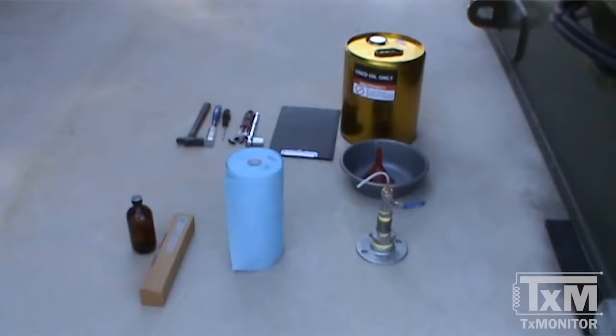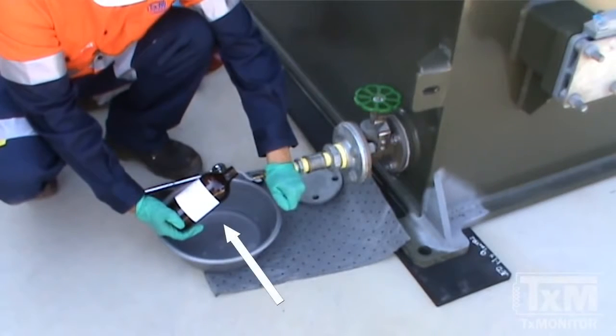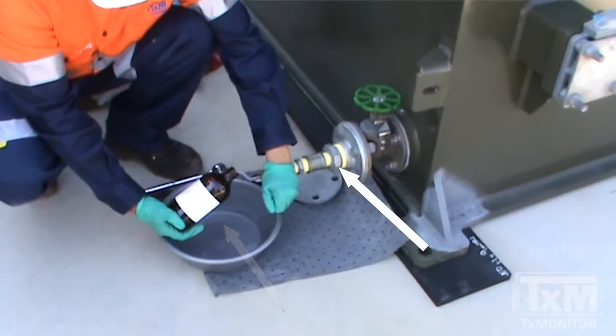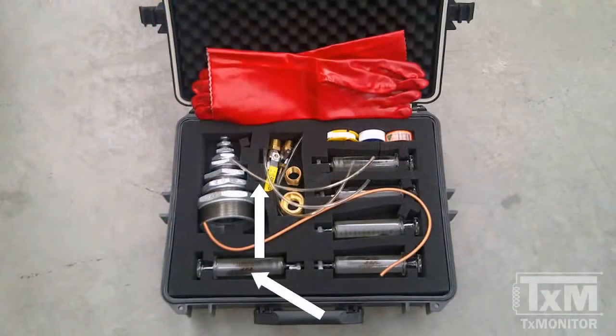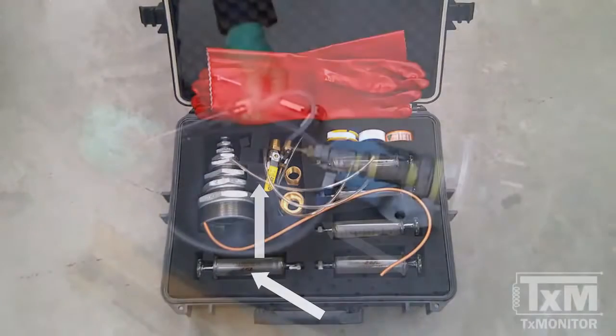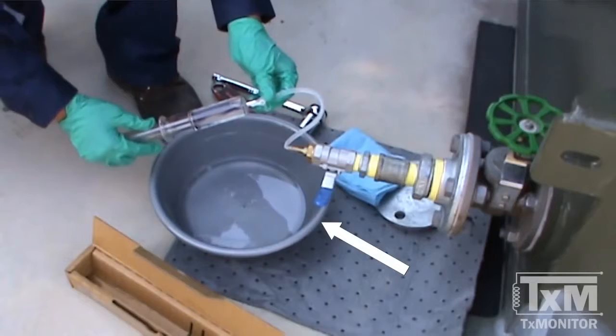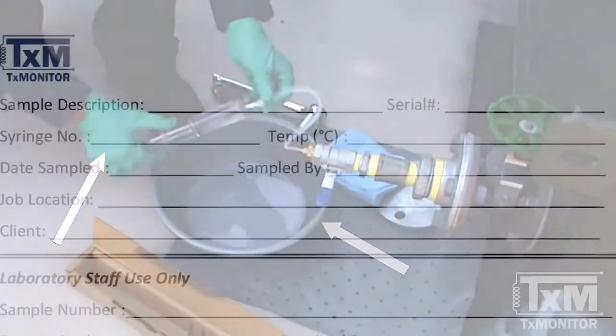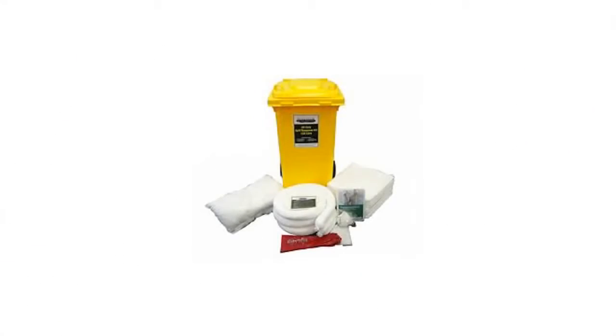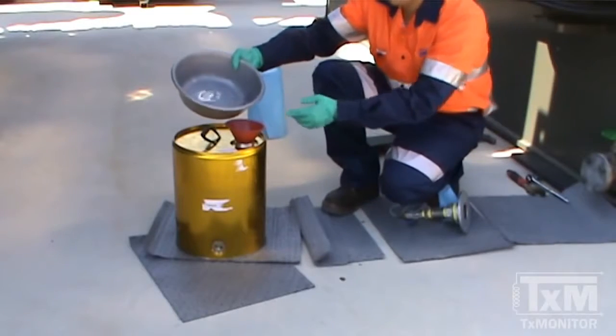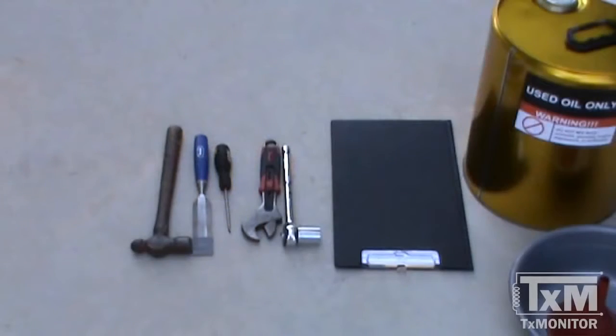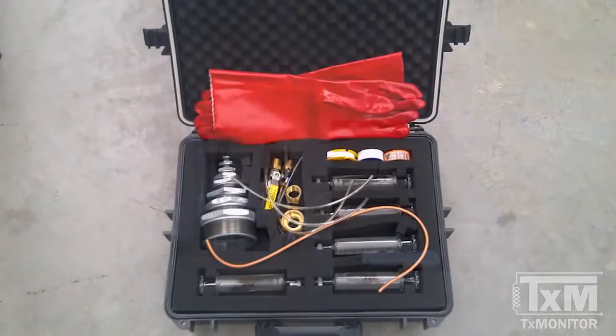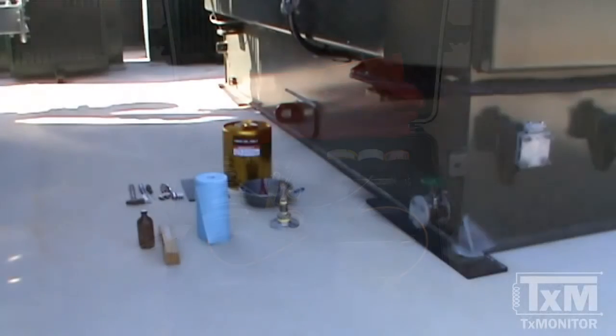Prior to mobilizing to site, ensure you have these essential tools and materials required for oil sampling: an amber glass bottle, sample adapter, silicone tubing, 50cc glass syringes, a container to capture oil waste during sampling, gloves, sample bottle labels, verification forms, a spill kit, a drum for storage and removal of oil, hand tools such as spanners and shifters, various size flanges, and rags.